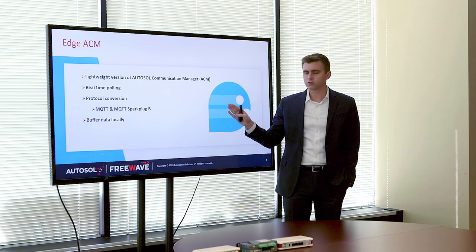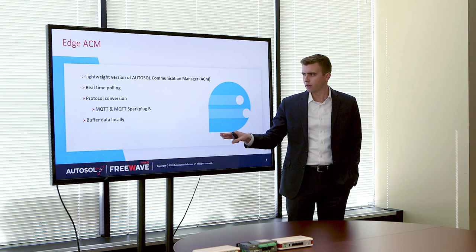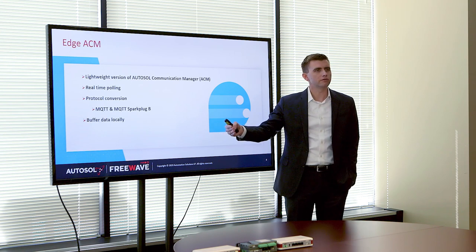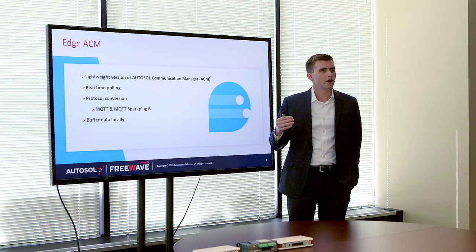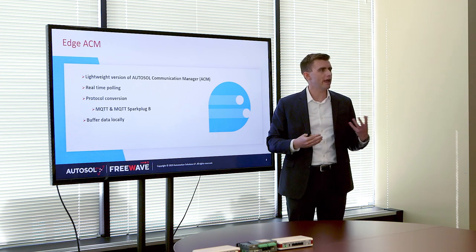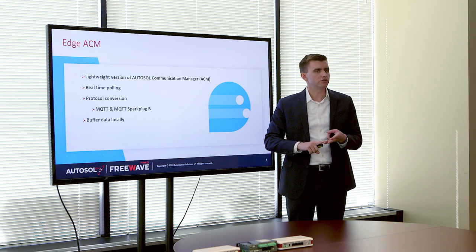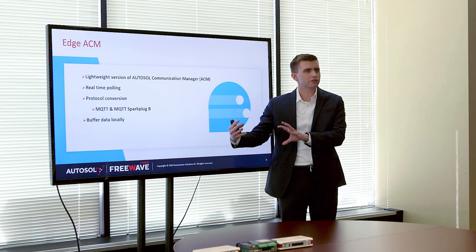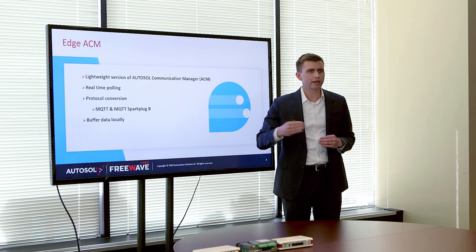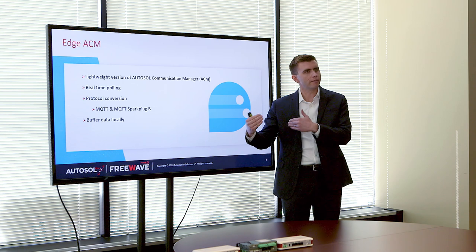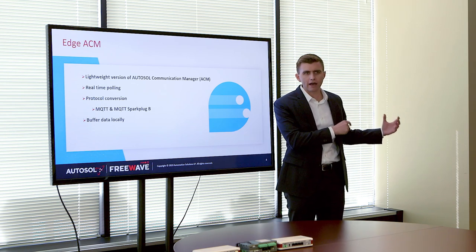Edge ACM does real-time polling of a number of protocols. It converts data from whatever protocol it is to MQTT or MQTT SparkplugB, allowing the user to innovate how they handle it with dead bands, with some edge alarming, as well as being able to put registers or tags in different tag groups and have those poll at different rates for more high-resolution data on what matters.